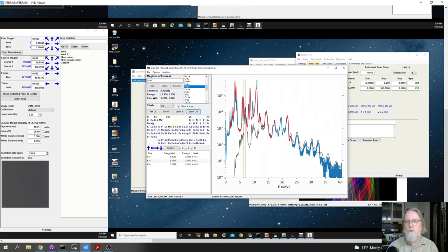So none of this stuff is real. It's just detector artifact that it couldn't count. It couldn't tell that it wasn't a 21 keV x-ray. It probably thought it was really two 11 keV x-rays from the Compton and elastic scatter. And there's a peak at twice the zinc energy and so on. And all of these peaks are from multiples of those.